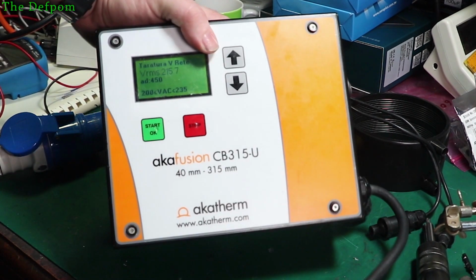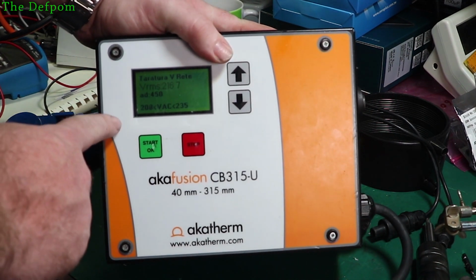I did those three, and then I did the 2100, and then I noticed the maintenance alarm had stopped. So one of those resets, and possibly the sequence of those resets, cleared the maintenance alarm. Through from 1000 to 3000, done every single code, and I'm working through now from zeros through to 1000 to fill that gap in. So now I would have done from 0 to 3000 codes and found everything that's in there. Anyway, what I wanted to comment on was on here, I did show you this before.